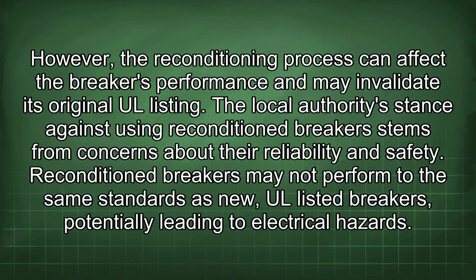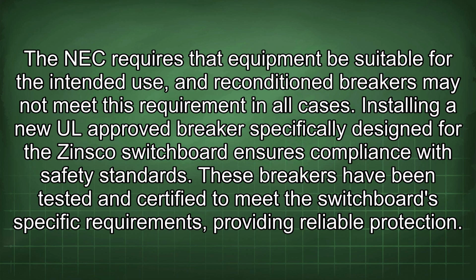The local authority's stance against using reconditioned breakers stems from concerns about their reliability and safety. Reconditioned breakers may not perform to the same standards as new, UL-listed breakers, potentially leading to electrical hazards. The NEC requires that the equipment be suitable for the intended use, and reconditioned breakers may not meet this requirement in all cases.